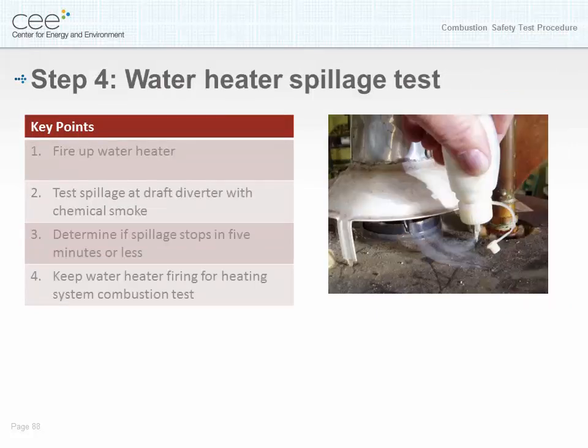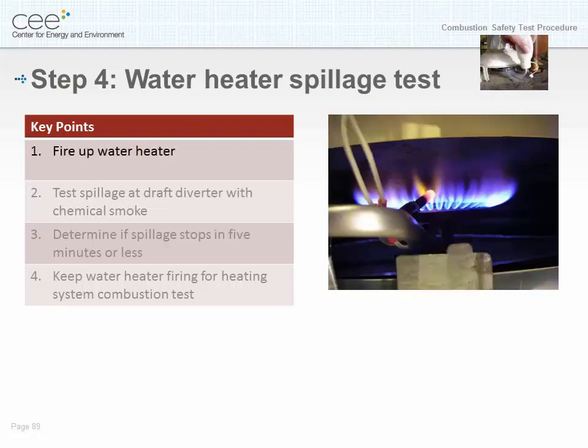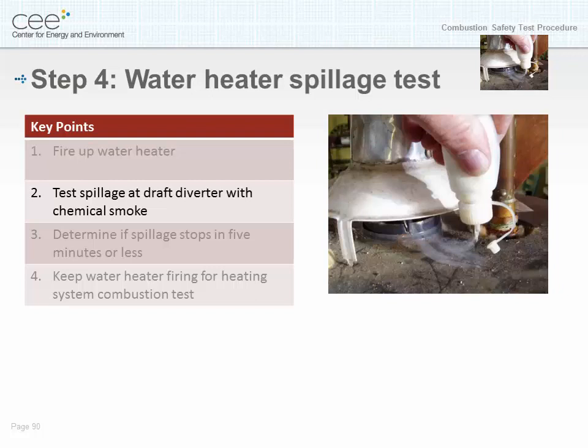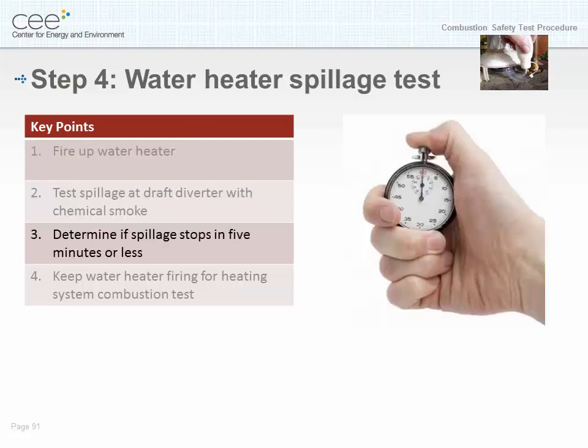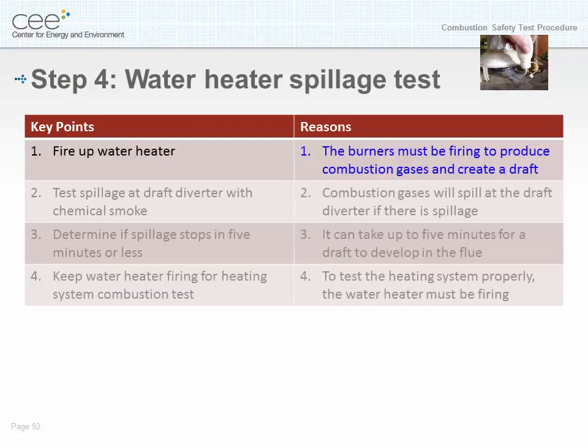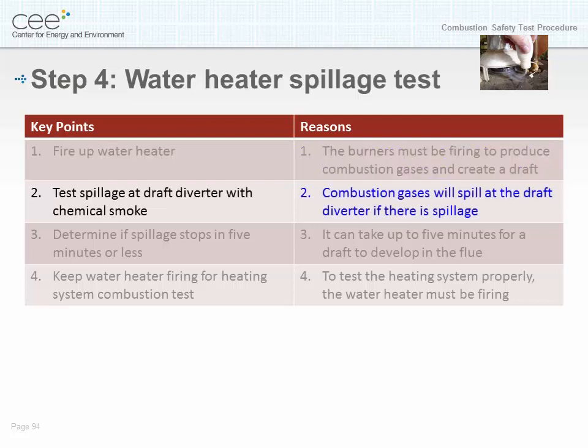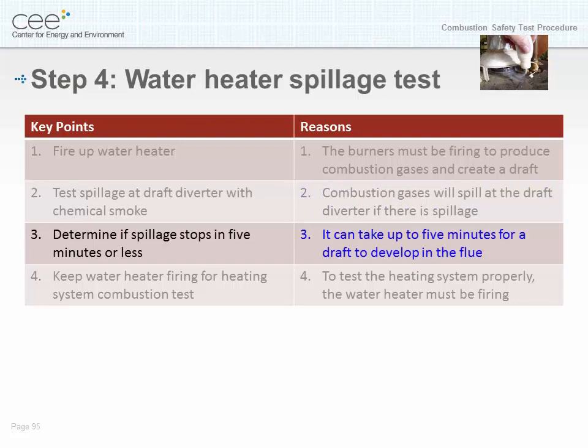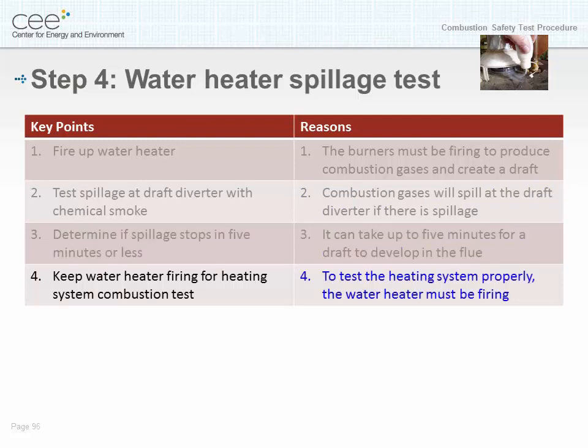Step four: water heater spillage test. Key points: number one, fire up the water heater; number two, test spillage at the draft diverter with chemical smoke; number three, determine if spillage stops in five minutes or less; number four, keep the water heater firing for the heating system combustion test. Reasoning: the burners must be firing to produce combustion gases and create a draft; combustion gases will spill at the draft diverter if there is spillage; it can take up to five minutes for a draft to develop in the flue; and to test the heating system properly, the water heater must be firing.